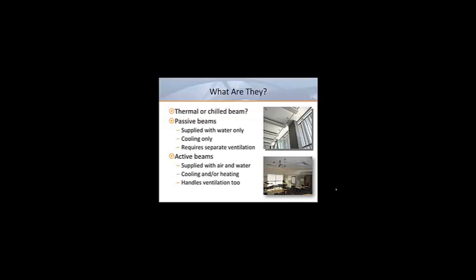This means that a separate ventilation system and outlets must be required. Since passive beams are typically ceiling mounted, they are most frequently used to provide only supplemental cooling to a space. Most of the recent interest in chilled beams comes from the wider possibilities that active beams present to the designer. Since both water and air are supplied to the active beam, it can address both the thermal and ventilation needs of an occupied space.